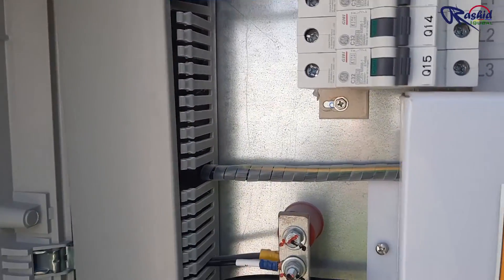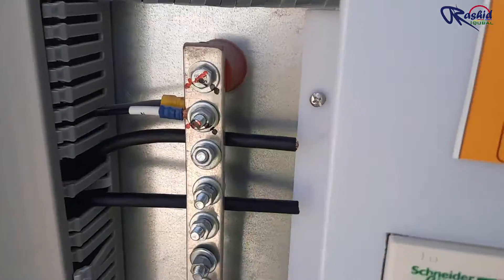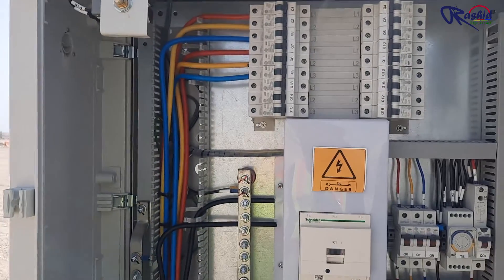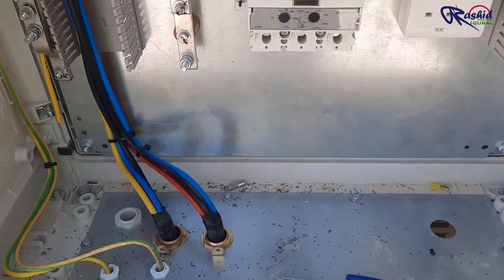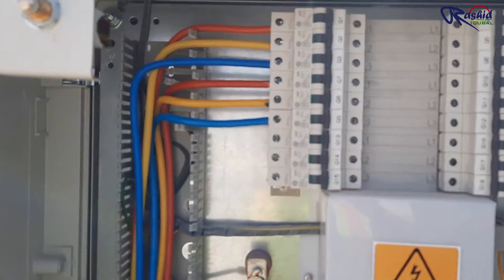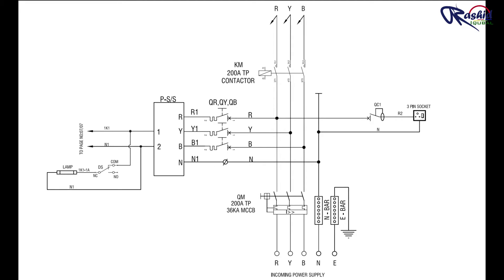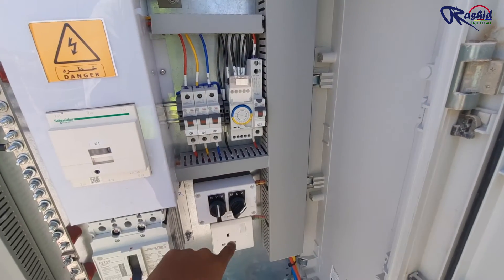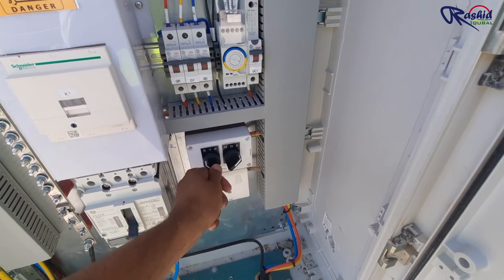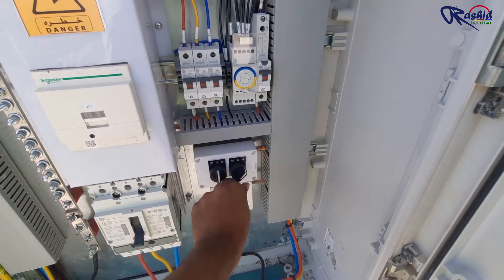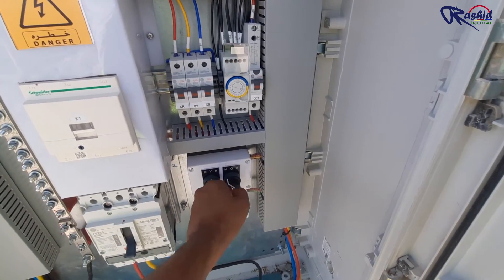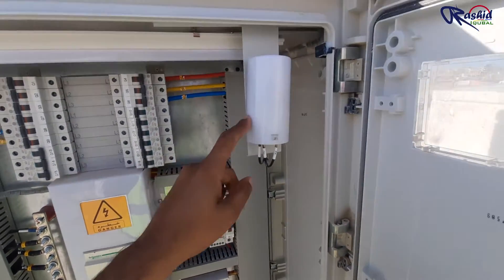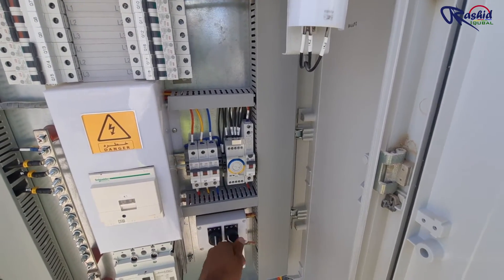Now let me show the wiring termination of this feeder pillar. These are the outgoing cables connected to the street lights. This is an auxiliary power supply for the control circuit, and here is the RCCB connected to the switch socket, which is installed here for maintenance purposes. This is a phase selector switch for control wiring and this is an auto/manual selector switch. If we flip the knob towards auto mode, the system will work through the timer and photocell, while in manual mode the contactor will directly energize and the street light will turn on.